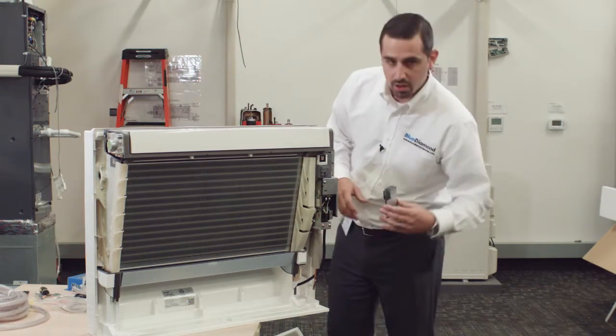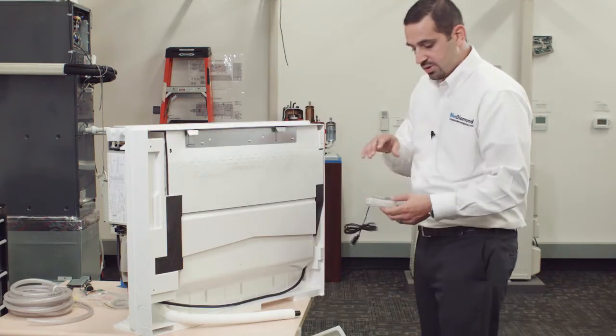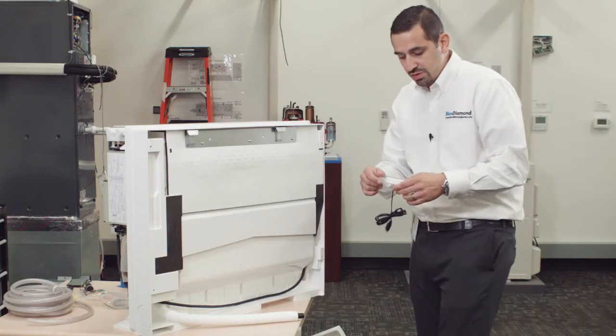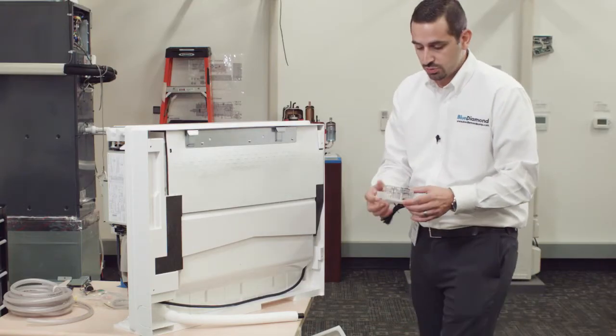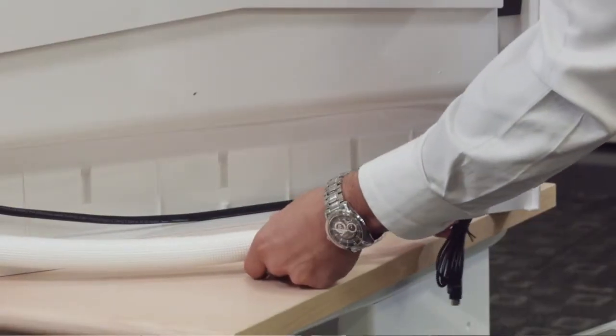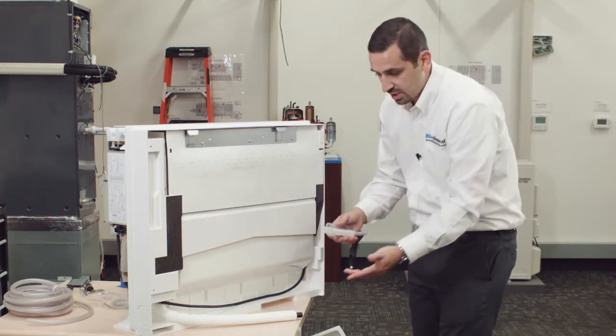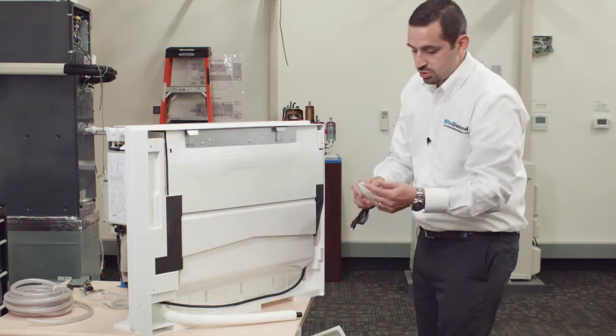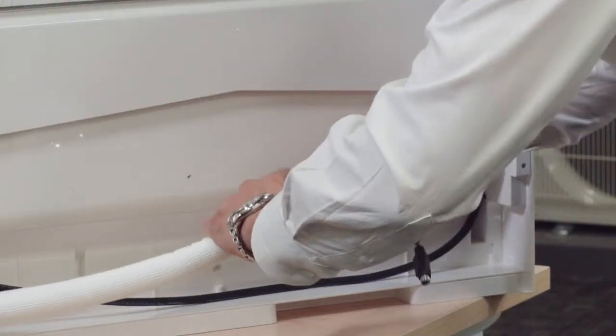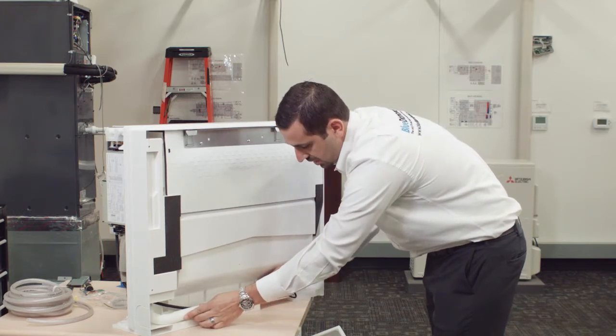To get started with the plumbing, we want to adapt our reservoir to the drain line. We're going to provide you with a half inch ID coupling which I've already trimmed down a little bit so we can get it as snug to the drain line as possible. We're going to use this coupling to adapt to your drain tube. Please note we do want to secure these connections to make them air and water tight.